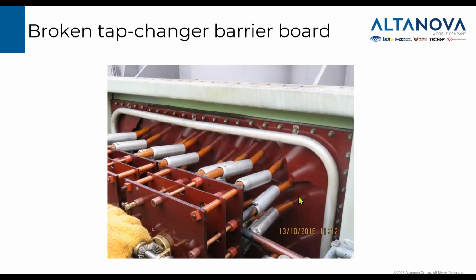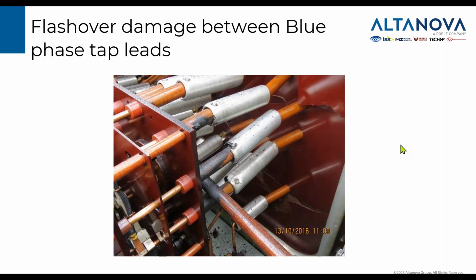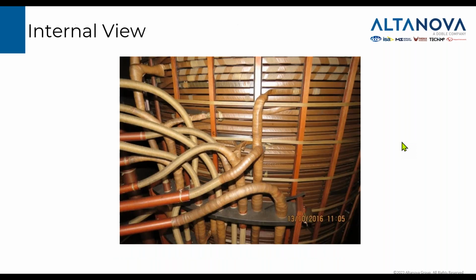And this is what we found. As I showed before, this broken barrier board. We have some deformations here of the leads connecting the winding through the barrier board to the tap changer, and some flashover marks on the C phase. Here we can see them better. And this is what was found in the winding. So this is our regulating winding with some flipped leads as seen in this picture.